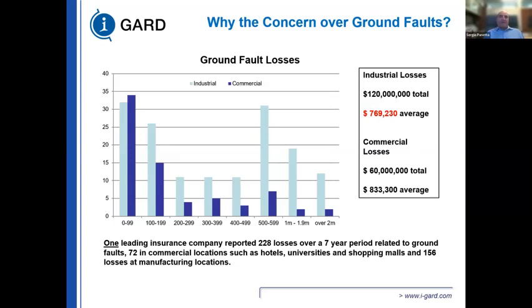Ground faults are said to be the most typical fault you can have in an electrical system. Some say over 95% of all faults begin as single phase to ground faults, and they propagate to a phase-to-phase or three-phase fault, and then you have an arc flash event. We can discuss that to some extent. And John, you mentioned you have Z462 and 70E training. Z462 and 70E both state that high resistance grounding is an arc flash mitigation technique, and we're going to discuss that to some extent.